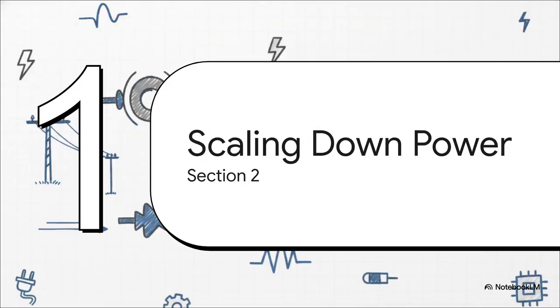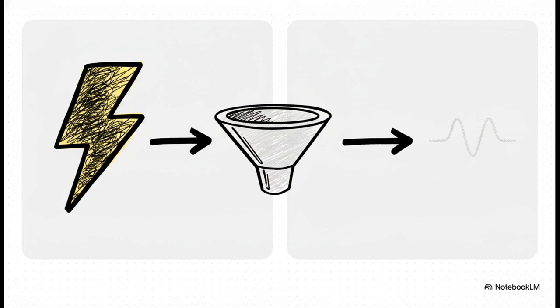Which brings us to Part 2, scaling down dangerous power. Out in the primary switchyard, you are dealing with incredibly huge, dangerous power. It's intense. That energy has to get physically scaled down by the CTs and VTs into small, safe, readable metrics for the relay's input ports. The physical ratio of the transformer out in the yard is doing all the heavy lifting here, delivering a completely safe secondary output directly to your relay panel.